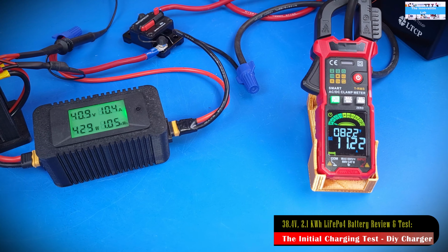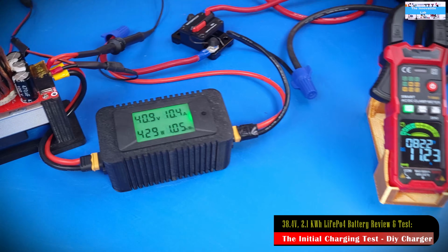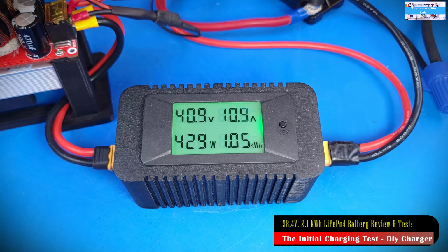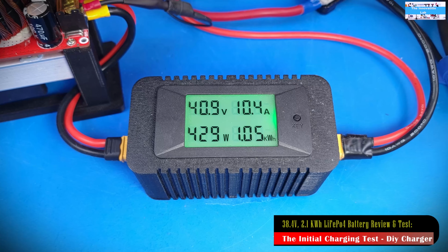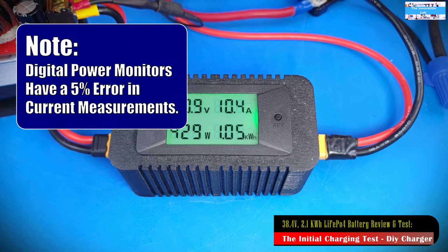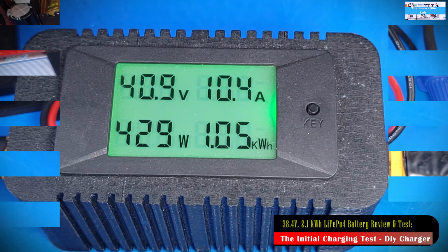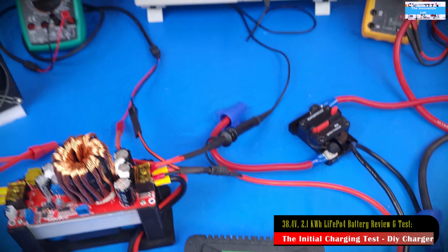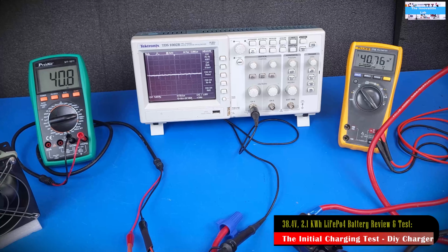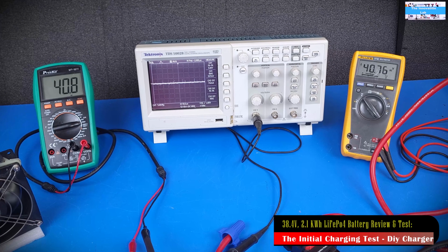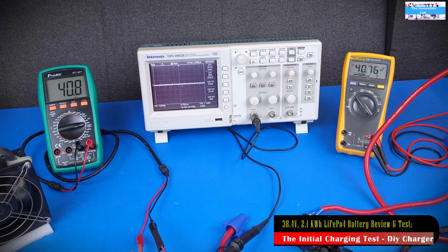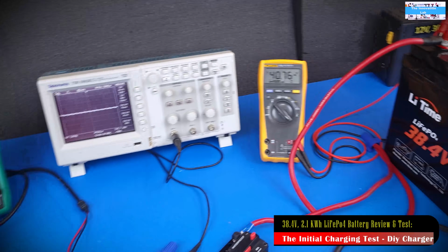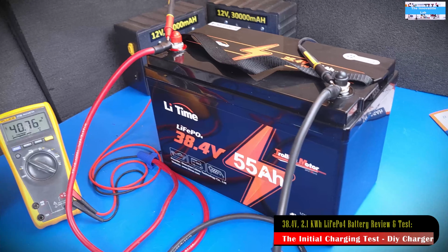One thing I did was add a digital power monitor to the system. The sole goal of adding that during the charge cycle is to keep an eye on the accumulated power the battery was able to take in during the charge phase, which helps us verify the battery capacity and make sure it matches the manufacturer rating.